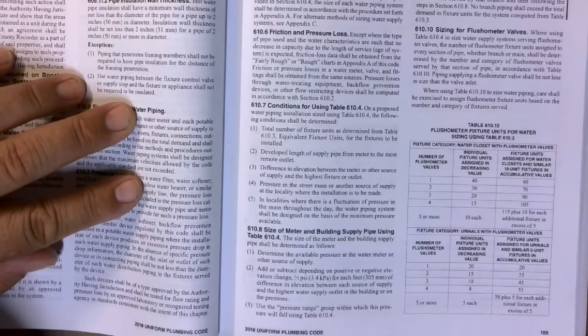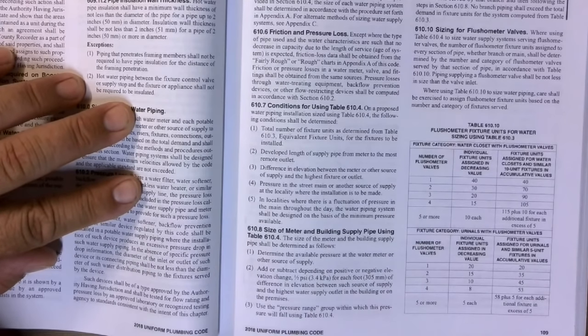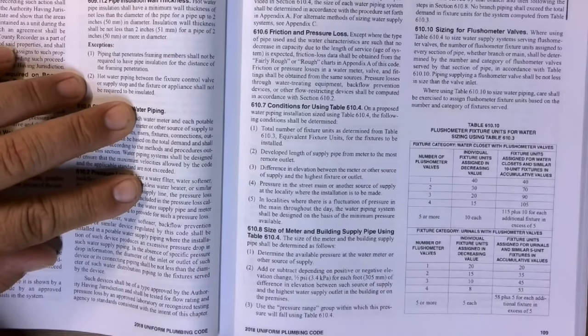Number 3, difference in elevation between the meter or other source of supply and the highest fixture or outlet. Number 4, pressure in the street main or another source of supply at the locality where the installation is to be made. So we have to know what kind of pressures we're working with, right? In localities where there is a fluctuation of pressure in the main throughout the day, the water piping system shall be designed on the basis of the minimum pressure available. We use the minimum pressure because that's the lowest pressure we can possibly operate at. If we sized everything at the highest and then all of a sudden you have a 20-pound drop in pressure every day, it can't keep up when it's at the lowest. So you always size to the lowest pressure available.